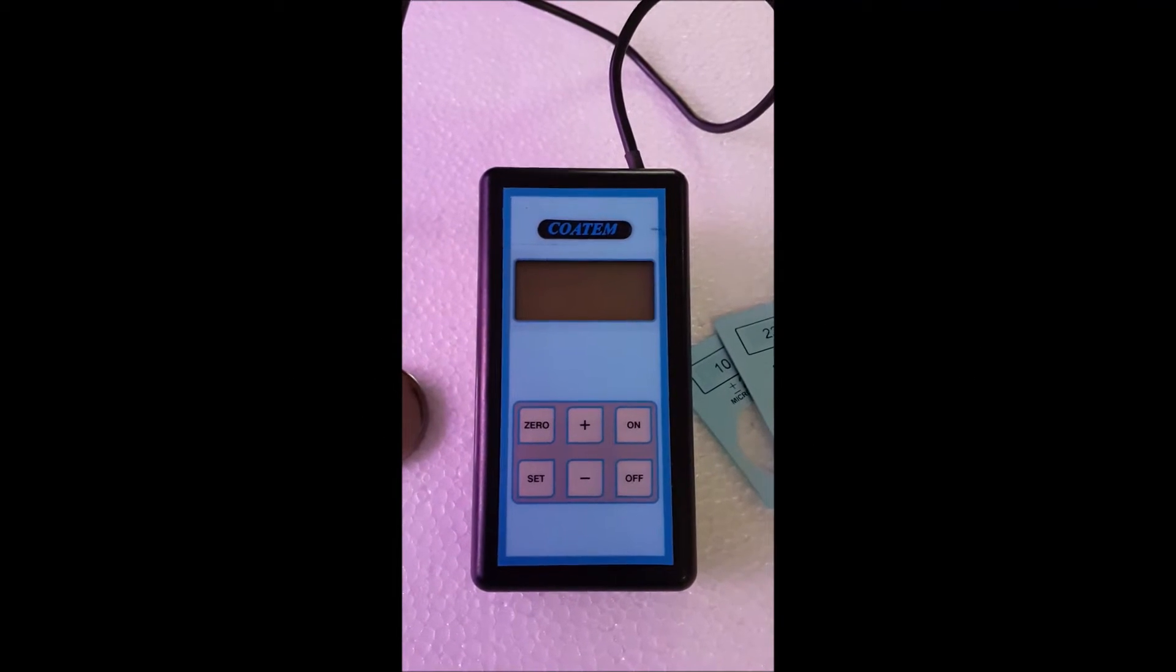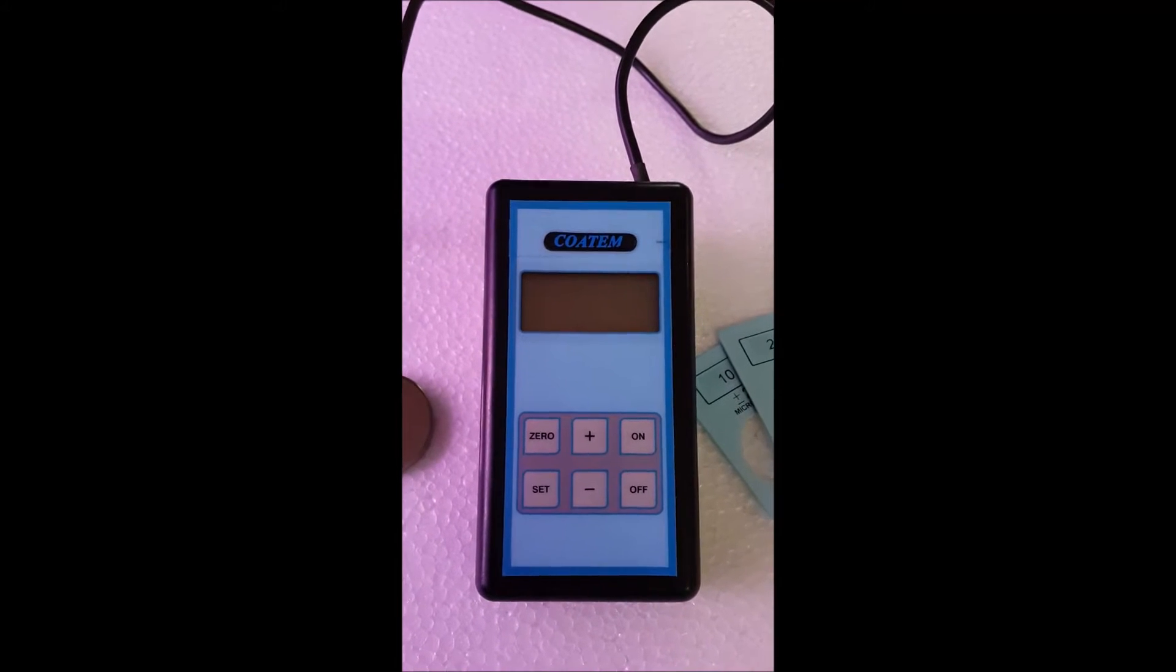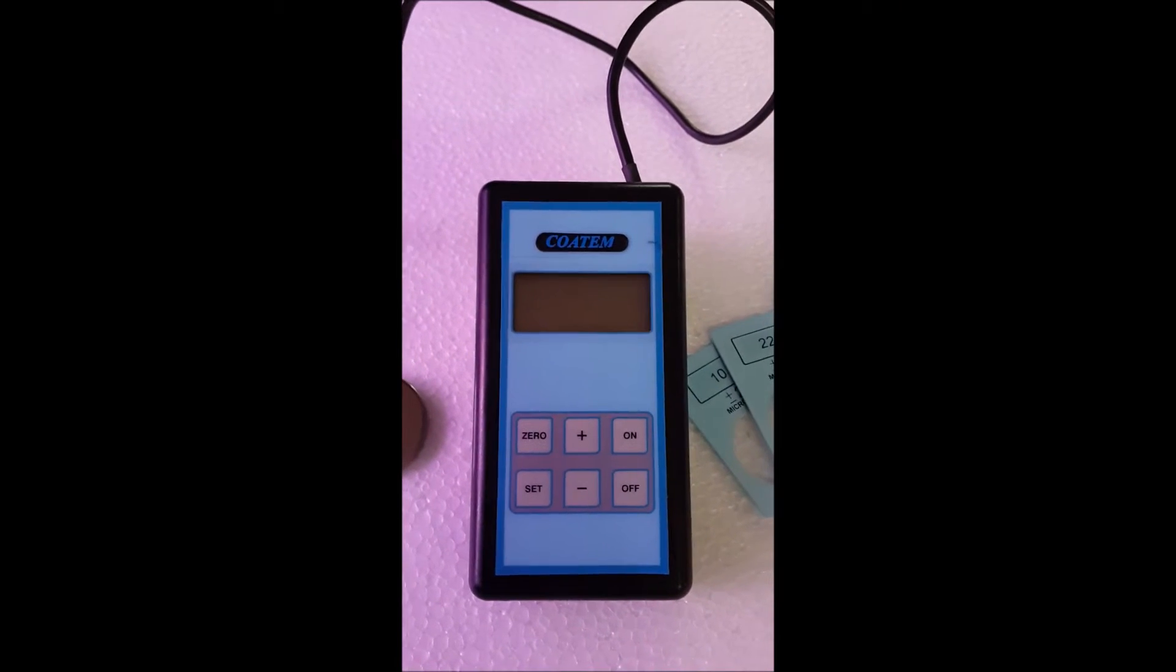This is a coating thickness gauge model Coatem. The range is 0 to 1500 microns and the resolution is 1 micron.